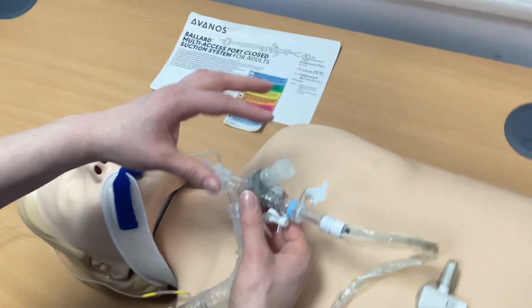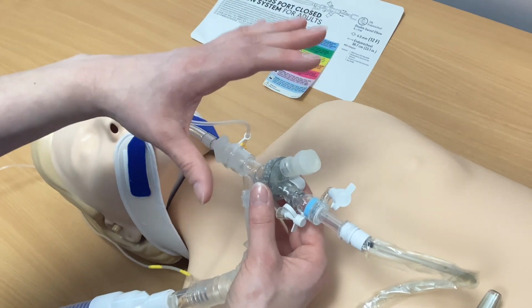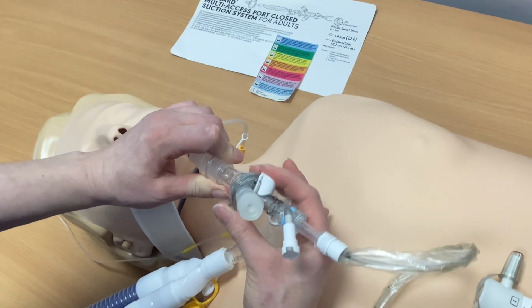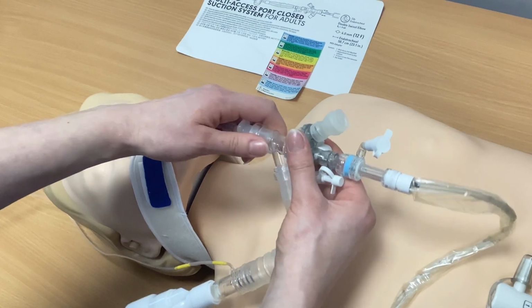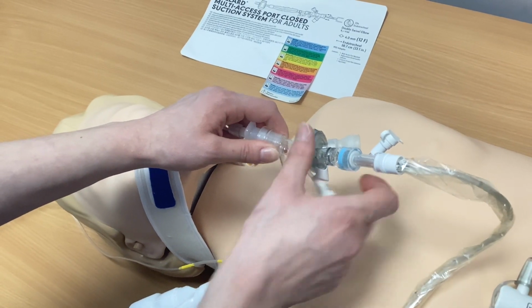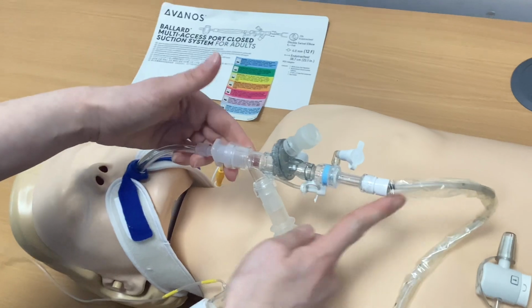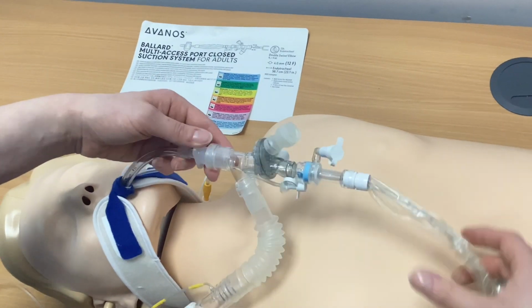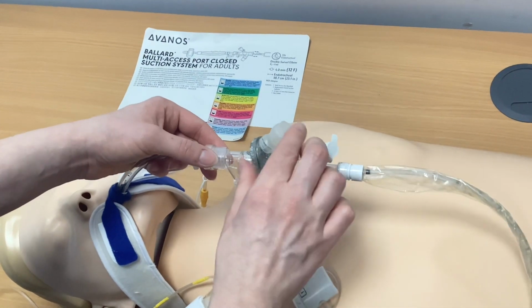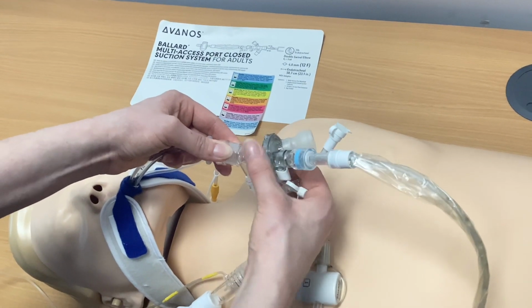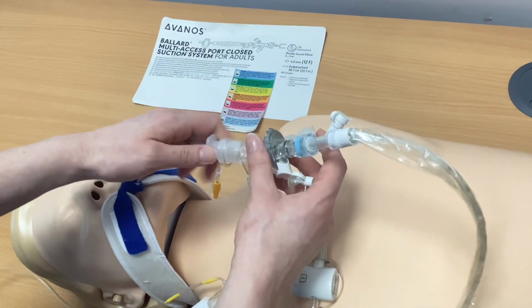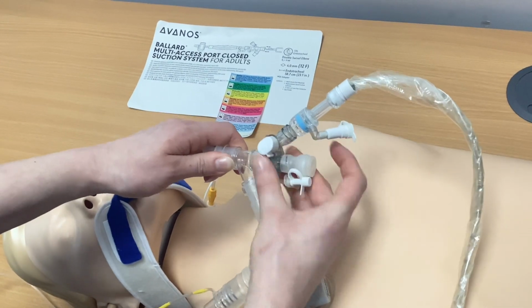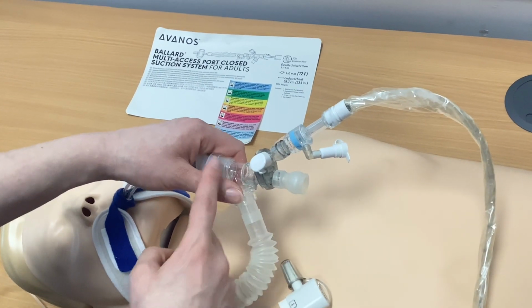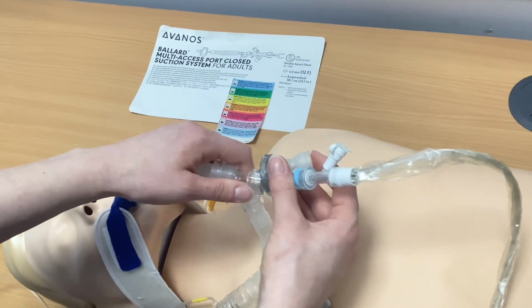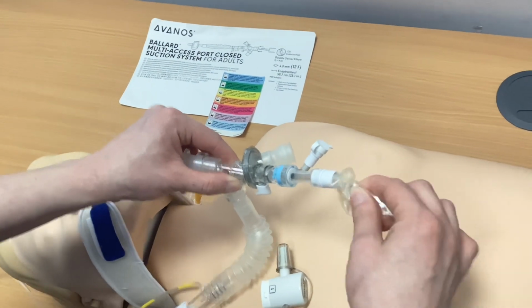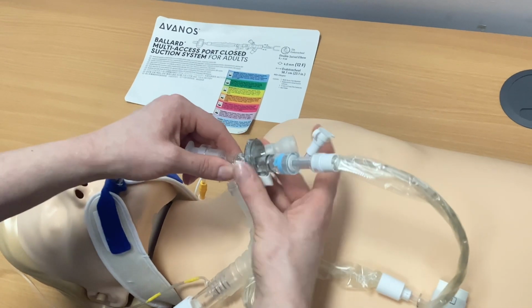What I'm going to talk about next is how to access the bronch port and the neutral position. This white button is how you will access these positions. As you can see, the whole suction catheter and tube is all in line, and this is how you are able to access the suction. Spin the multi-site a quarter turn clockwise to access the neutral position. Spin the multi-site a further quarter turn clockwise to access the bronch position. When in the bronch and neutral positions, you will not be able to access the tube with your suction catheter.